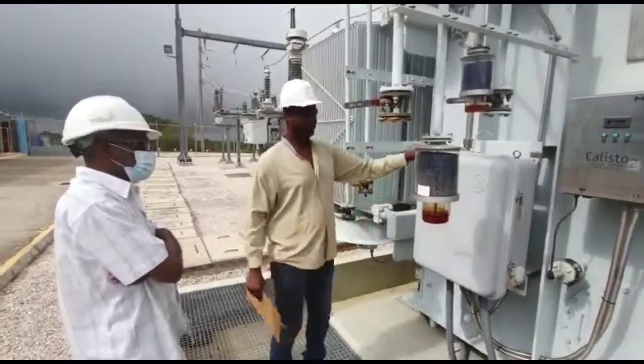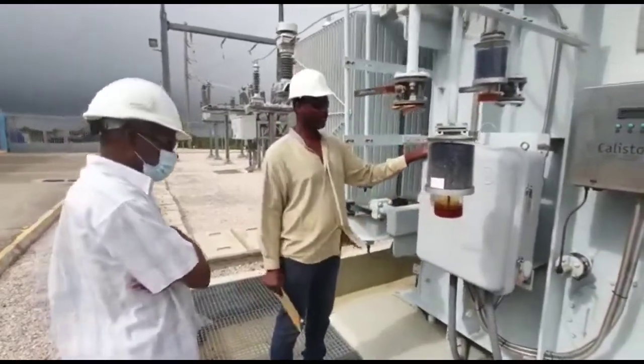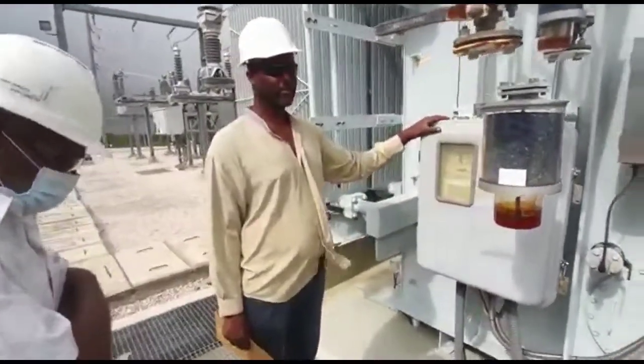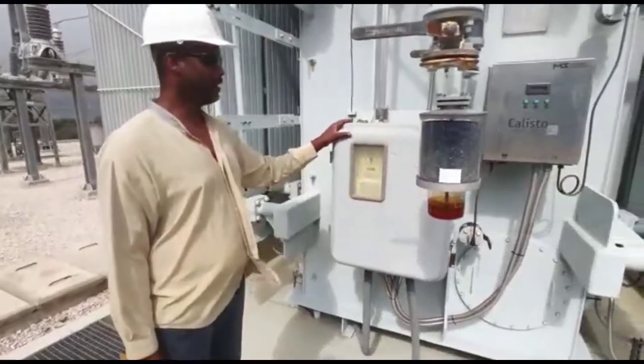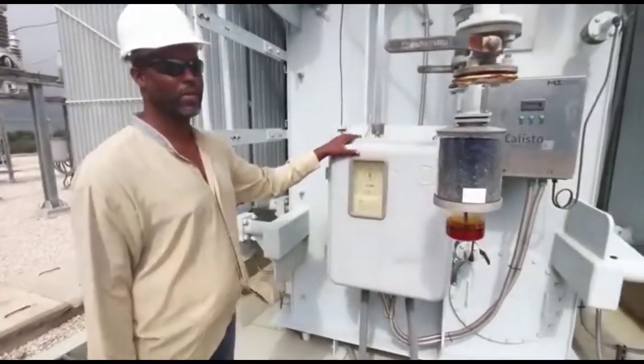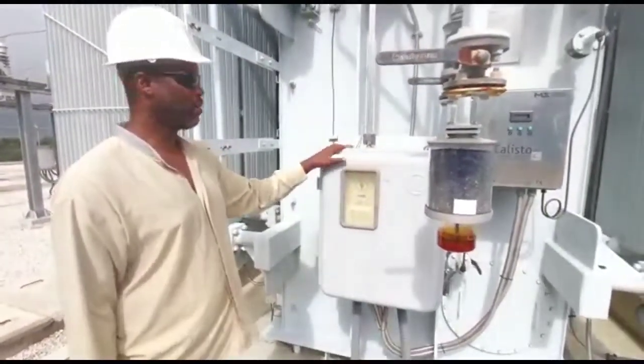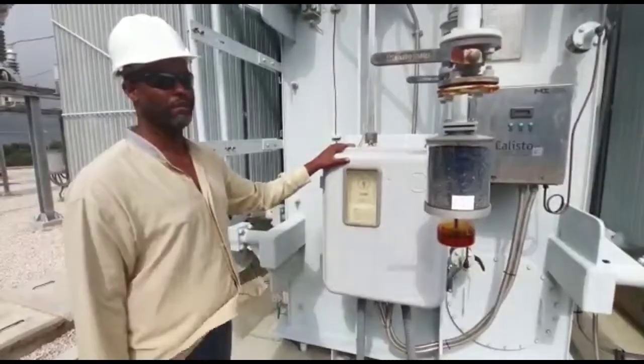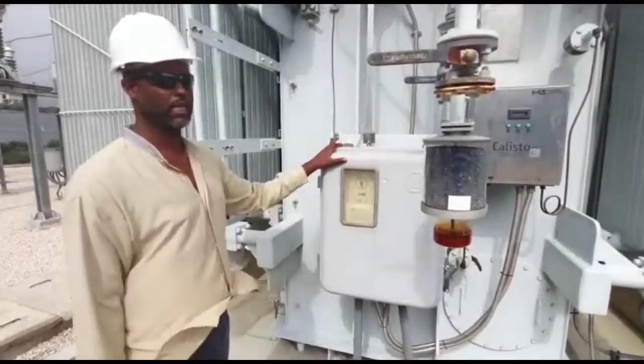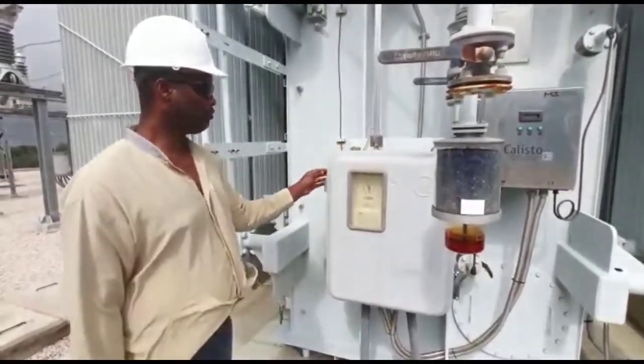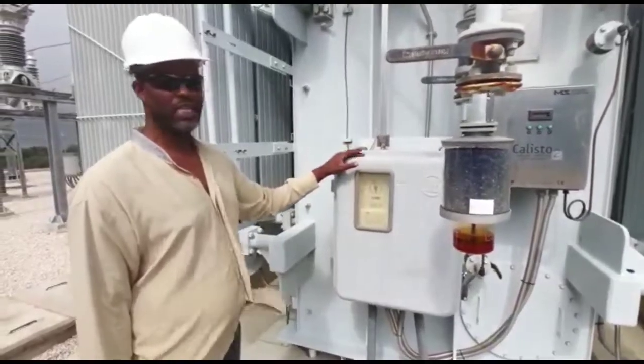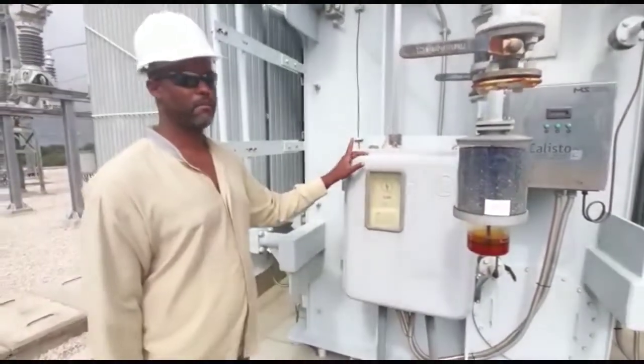Now here we have the online tap changer. The reason it's an online tap changer is because it can change without the transformer coming offline, meaning you don't have to turn off the transformer to change the taps.